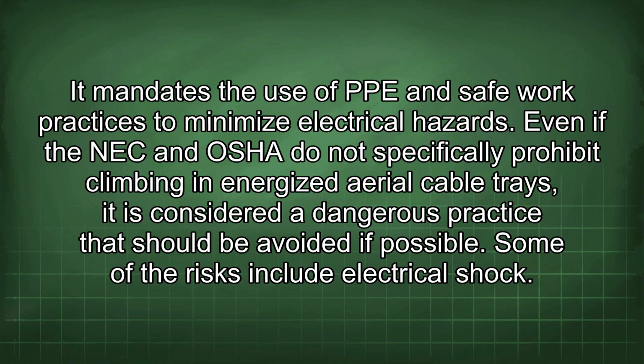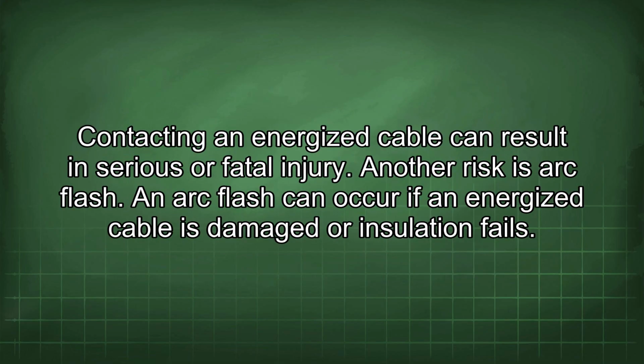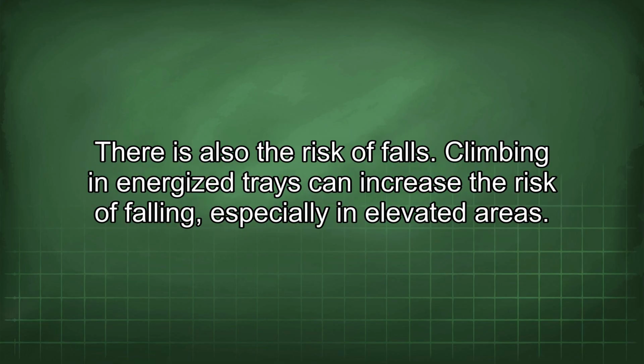Even if the NEC and OSHA do not specifically prohibit climbing in energized aerial cable trays, it is considered a dangerous practice that should be avoided if possible. Some of the risks include electrical shock. Contacting an energized cable can result in serious or fatal injury. Another risk is arc flash. An arc flash can occur if an energized cable is damaged or insulation fails. There is also the risk of falls. Climbing in energized trays can increase the risk of falling, especially in elevated areas.